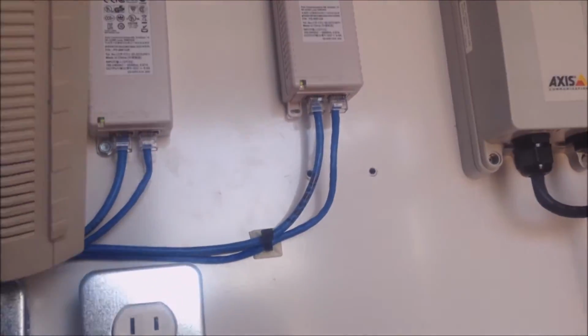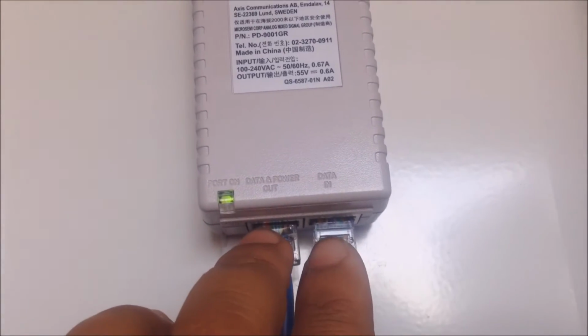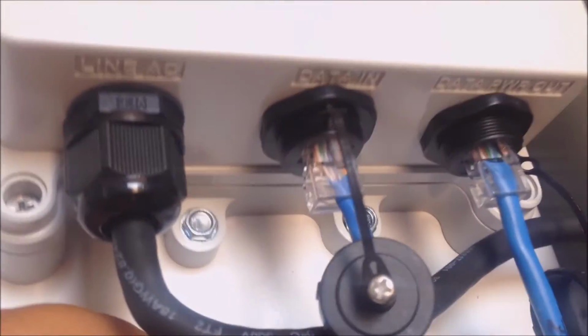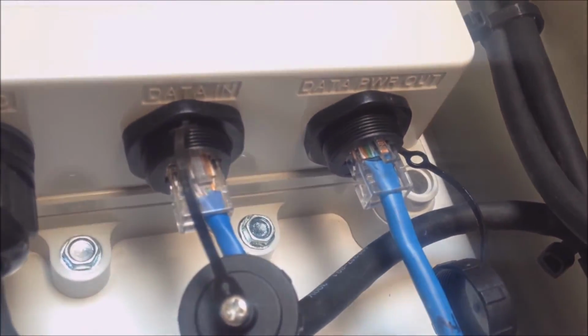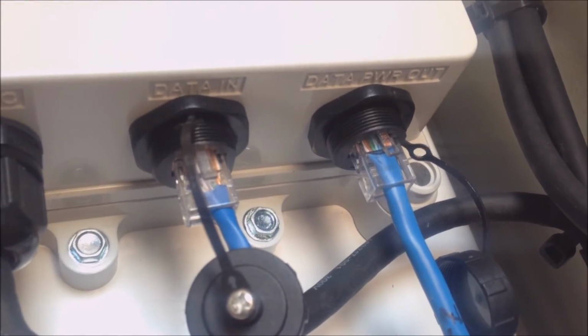60 watt outdoor, we're using that for a PTZ camera. Here is the cable with data and power out, that is going out to the camera. Data in would be going to your switch or to your laptop. The data and power out is on the right side here of the 60 watt outdoor. We're using Cat 5E, but we do recommend Cat 6 cables.